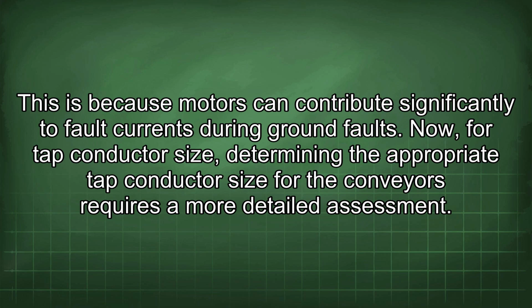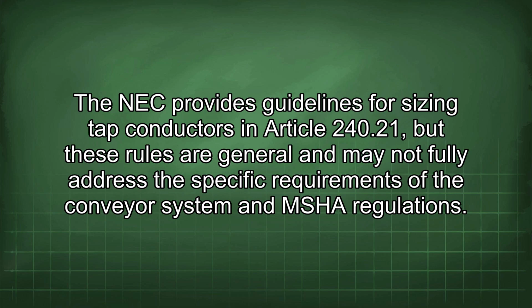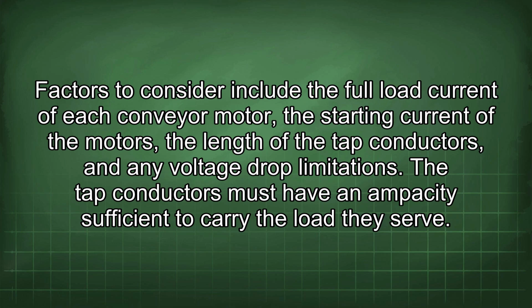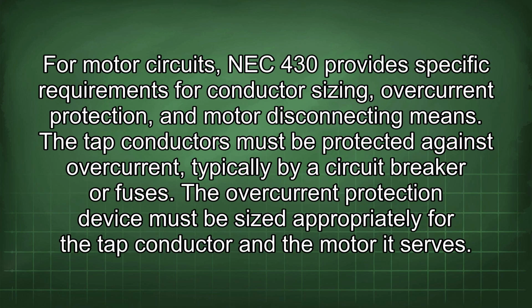Now, for tap conductor size, determining the appropriate tap conductor size for the conveyors requires a more detailed assessment. The NEC provides guidelines for sizing tap conductors in Article 240.21, but these rules are general and may not fully address the specific requirements of the conveyor system and MSHA regulations. Factors to consider include the full load current of each conveyor motor, the starting current of the motors, the length of the tap conductors, and any voltage drop limitations. The tap conductors must have an ampacity sufficient to carry the load they serve.